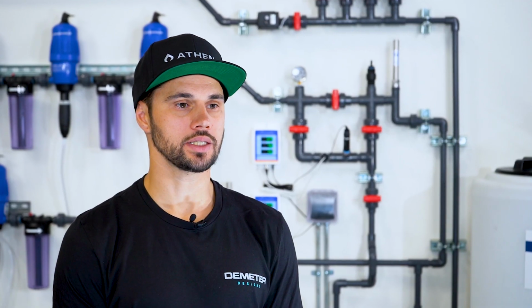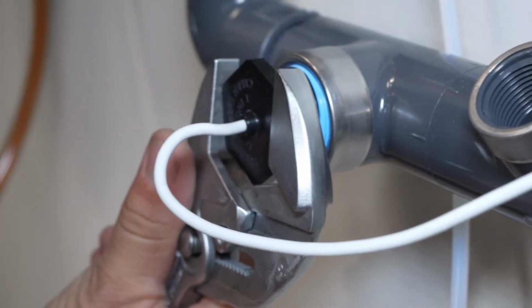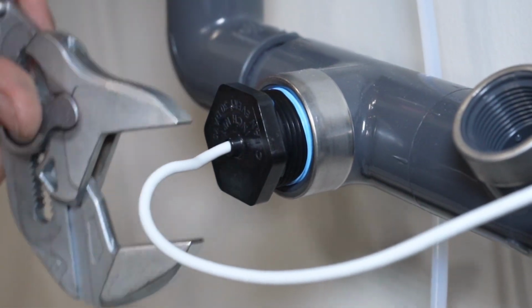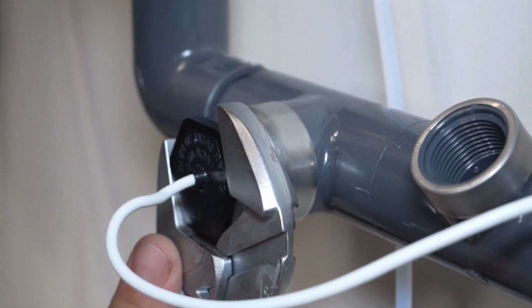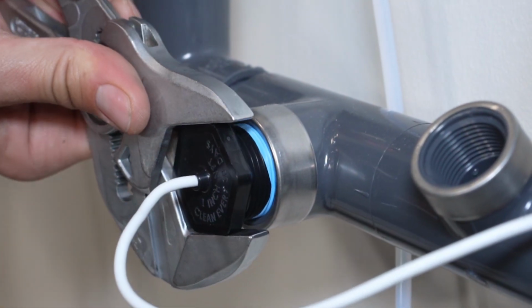The EC probe does not detach from the monitor. I like to pre-twist the wire 4 to 5 times in a counterclockwise direction before installing, so that when we're tightening the probe into the monitoring loop, it does not leave the wire twisted up when finished. This results in a cleaner installation.